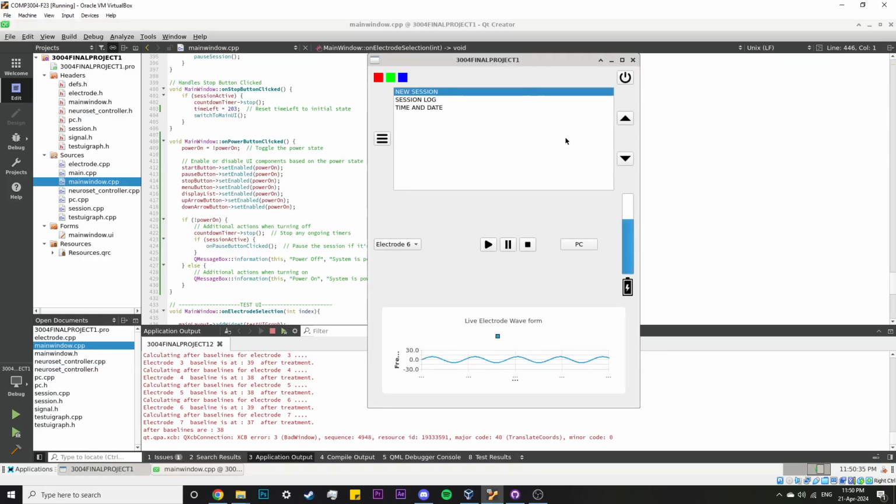As you can see, our app has multiple lights which signify different parts. What we care about is the red one, as it represents disconnected/low battery. Based on our use case, our app would continually monitor the connection between the electrodes and the device. The device would warn the user if disconnection is detected, which is shown through the red light at the top of our app. The user can reestablish the connection as the session is automatically updated. The device would store any session data and end the session if the connection is not made again.